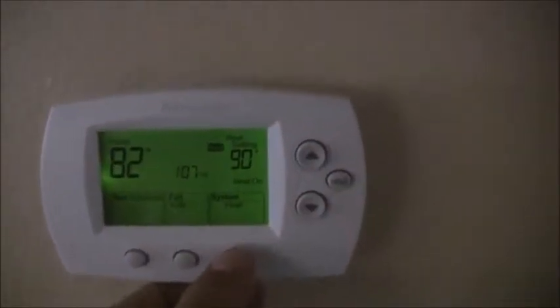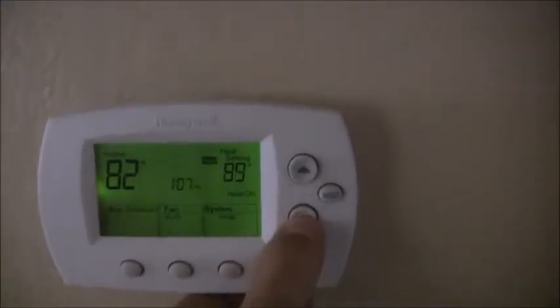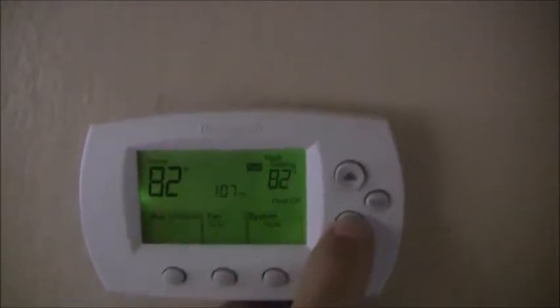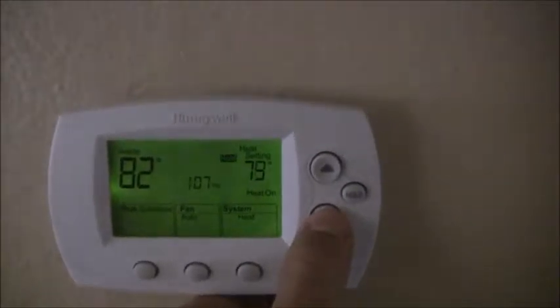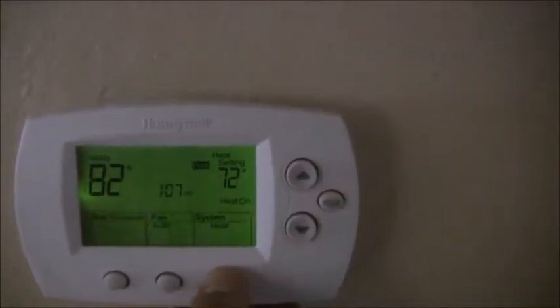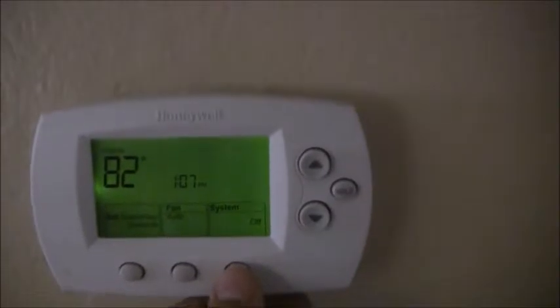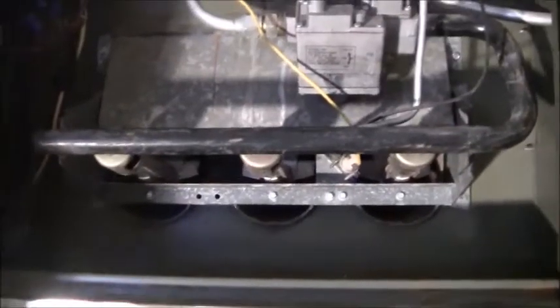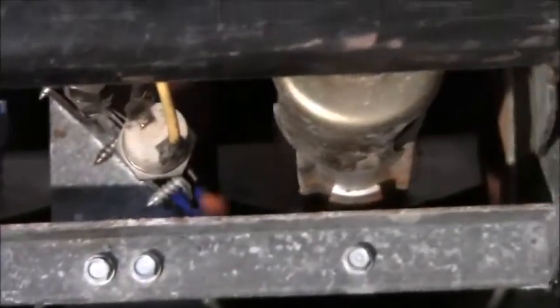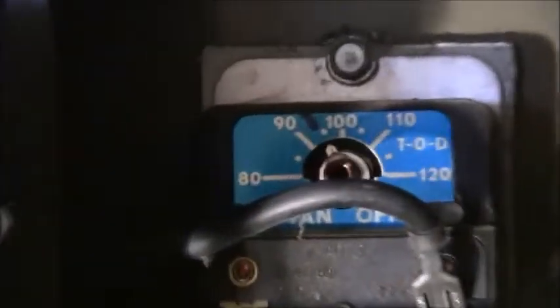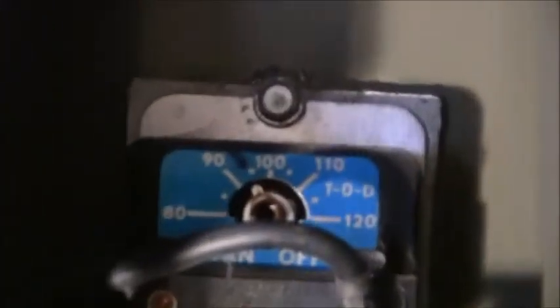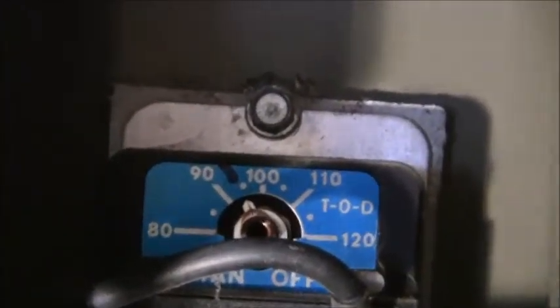Okay, we're back at the thermostat and let's lower this setting to a normal heat setting. It'll be something like 72. And I'm going to go to system off for now. Okay, with the thermostat off, the flame has shut off, but the blower is going to stay on, and it is going to stay on until the heat exchanger reaches the set point of 95 degrees Fahrenheit. At that point in time, it's going to shut off.